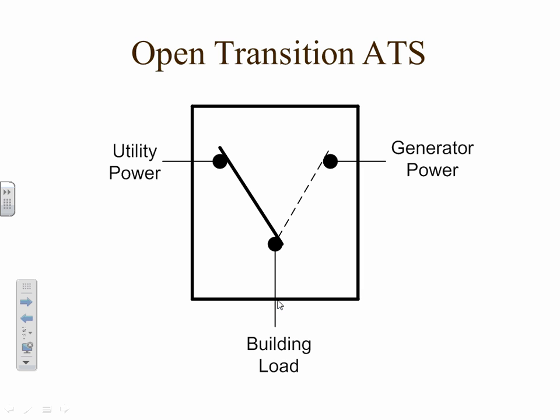But if you remember, I said this is a non-legally required system. A legally required system has to start and be online supplying power to the load in 10 seconds. So this one is not used a lot. But for homeowners, it's fine. Okay, it's not legally required. Harder on the equipment then? It's really not. It's not too bad, I don't think. Again, the engine's warm already from the water jacket heater, and that's the thing that you're really concerned about. So I question the validity of even having the thing, you know.